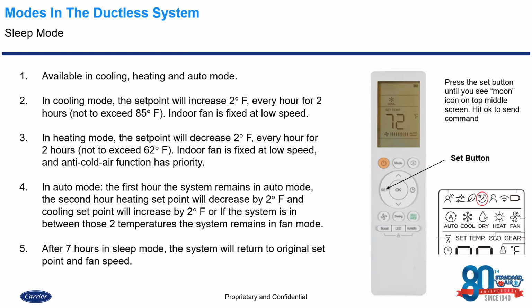In the heating mode, the set point will do the exact opposite, so it's going to decrease 2 degrees every hour for 2 hours, not to go below 62 degrees. If it goes below 62 degrees, it'll bring on the unit, warm it back up to 62, and maintain that threshold. That indoor fan is also fixed at a low speed, and the anti-cold air function has priority.